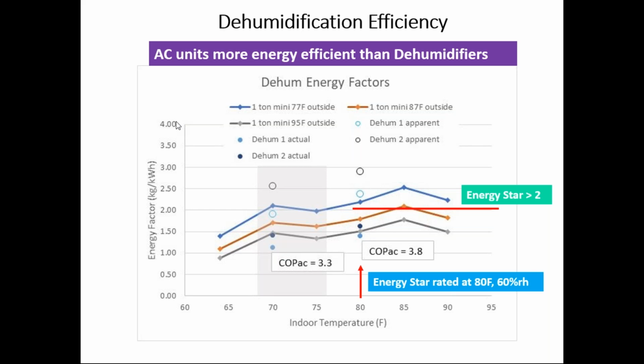And this energy factor for the Minisplit does not account for its sensible cooling. This is only looking at the amount of water coming out of it relative to the power to drive it. And so in effect, this is not directly apples to apples, but favors the dehumidifier unit. And if we added in that additional sensible cooling benefit, the Minisplit or standard air conditioner would look even better.